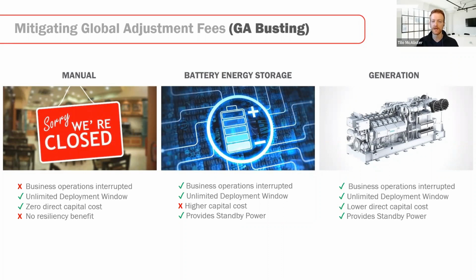Generators, from the simplest angle, I think are the easiest solution to this, because you can run them as long as you need to during a peak, and they're relatively cheaper compared to batteries. You can also have standby power for your entire load whenever you need it outside of these peak shaving events. So we see them as quite popular.